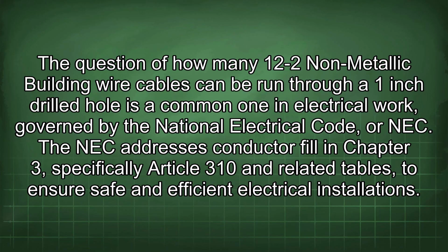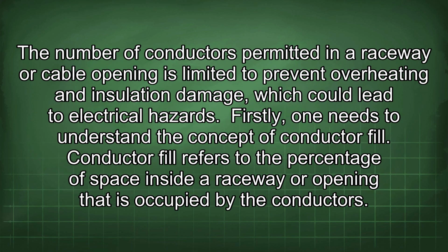The question of how many 12-2 Non-Metallic Building wire cables can be run through a 1-inch drilled hole is a common one in electrical work, governed by the National Electrical Code, or NEC. The NEC addresses conductor fill in Chapter 3, specifically Article 310 and related tables, to ensure safe and efficient electrical installations. The number of conductors permitted in a raceway or cable opening is limited to prevent overheating and insulation damage, which could lead to electrical hazards.